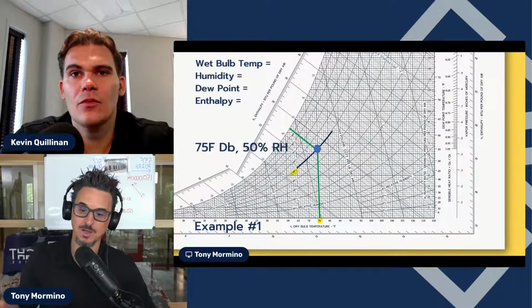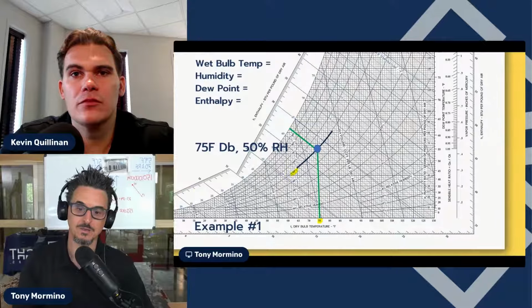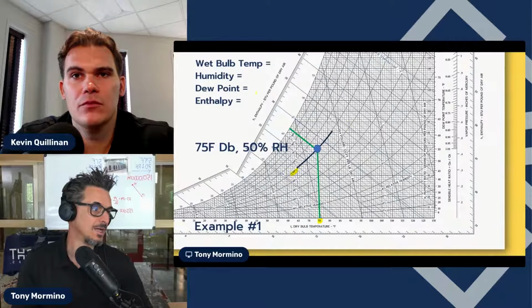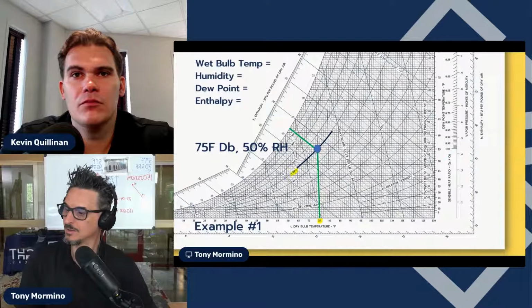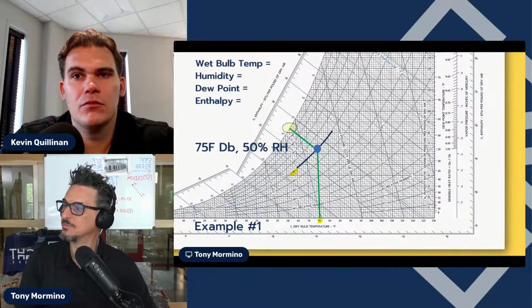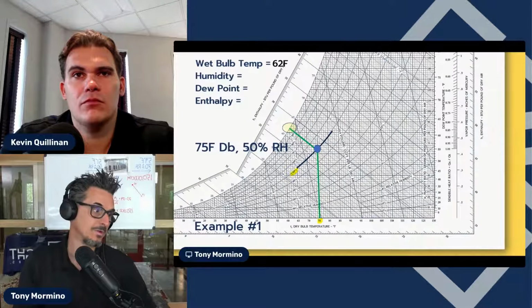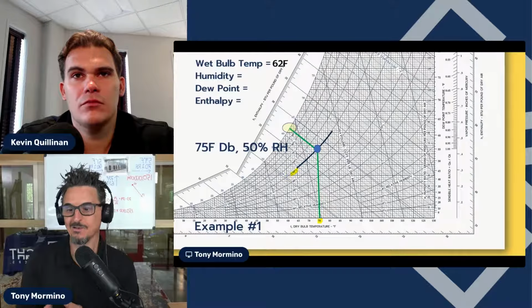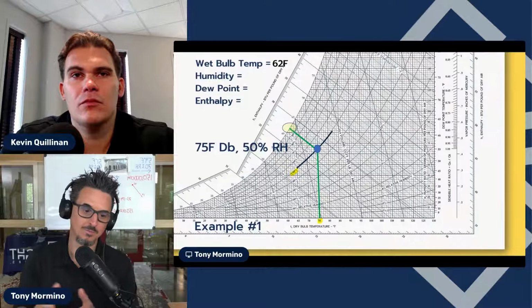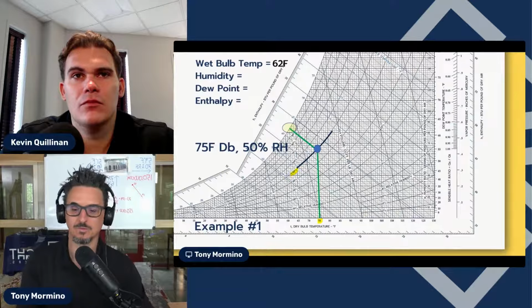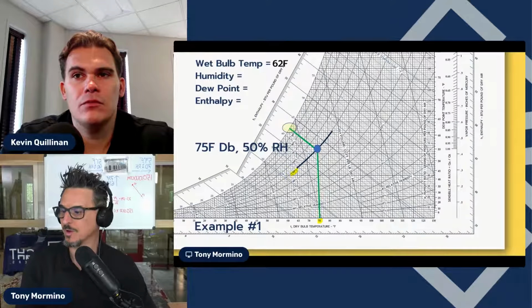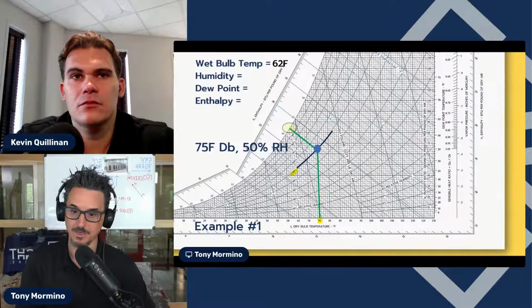So let's determine the wet bulb. You take this point and draw a line up to the wet bulb, circle it, and determine that it's 62 degrees wet bulb. So you don't have to have a reader at the job site that can pick up everything. You just got to get 2 points, and the easiest ones are usually dry bulb and relative humidity in my experience.